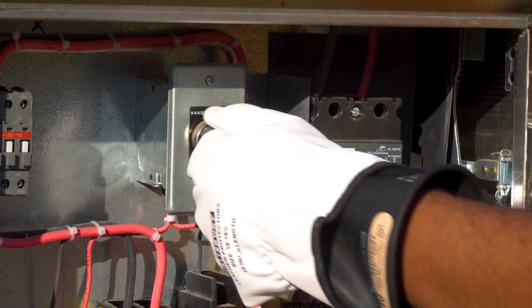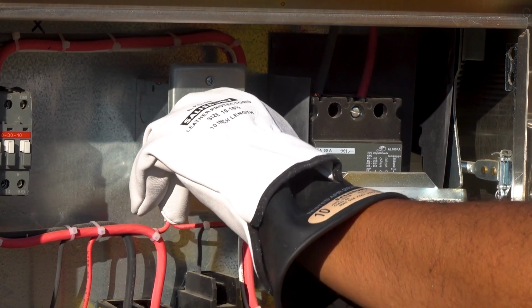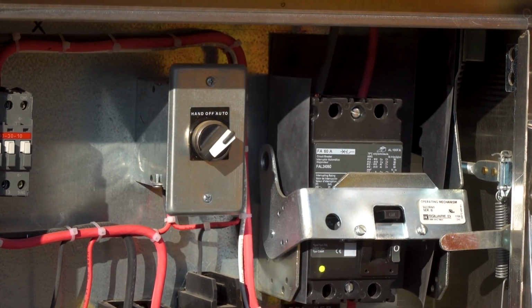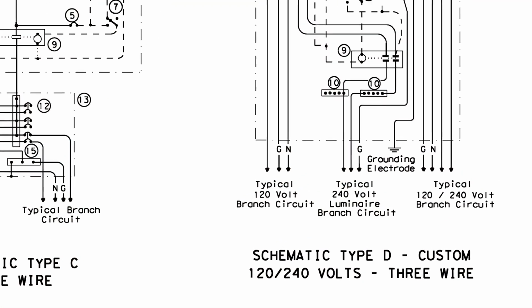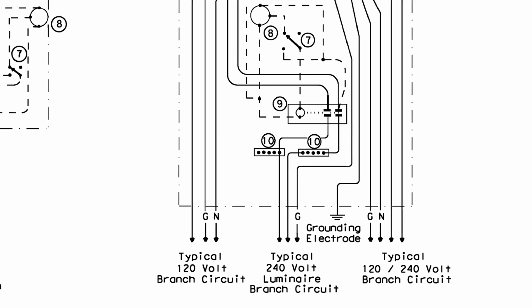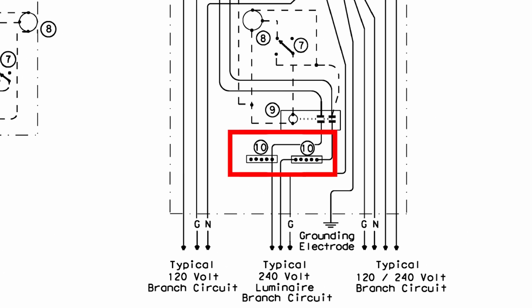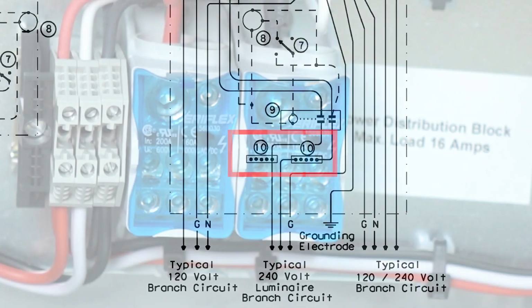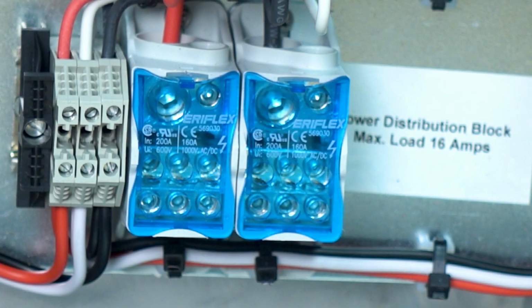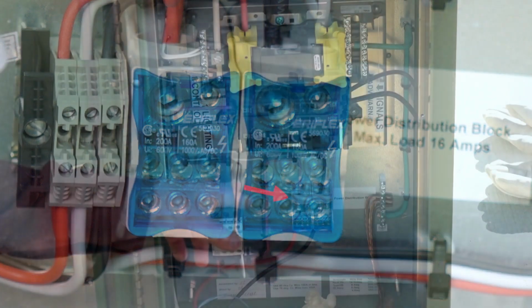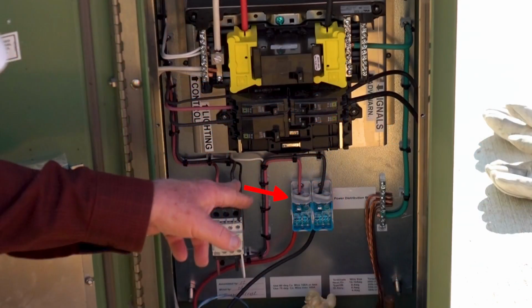Upon completion of this task, the handoff auto switch should be returned to the auto position. To reduce the number of conductors connected to the lighting contactor, power distribution blocks are installed. Power distribution blocks allow conductors from the lighting contactor to be connected to a common point so that power can be fed from the lighting contactor to multiple luminaires.